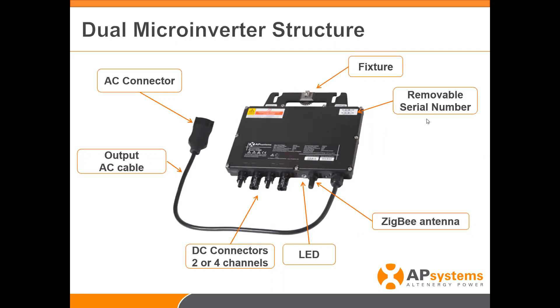Can you pop up the next slide, Jason? Thanks. So our bus cable can handle up to 20 amps and is compatible with all our current single-phase microinverters. One bus cable can handle 7 YC600, 6 DS3L, and up to 5 DS3D due to the higher output. Just make sure never to overcharge the bus cable beyond those 20 amps. We have this bus cable in 2 and 4 meter lengths between connectors. Crystal will tell us some more about that later on.